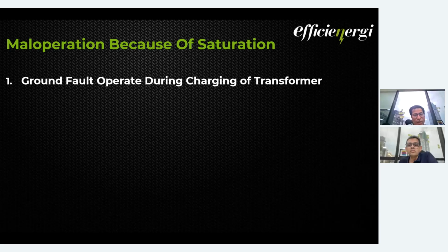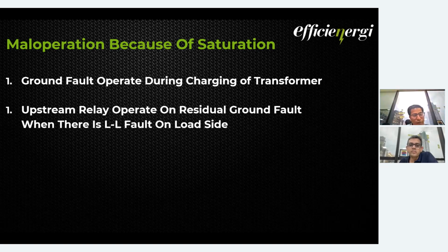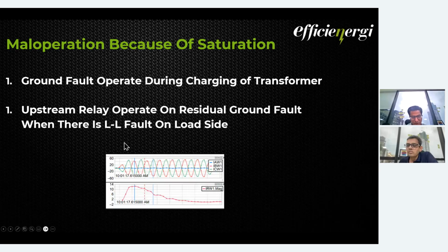Then there is a second case we see very often. That is when there is a line-to-line fault on a load side, but the upstream relay operates on residual ground fault. In the actual case, there is no ground fault happening on the load side. There is a simple line-to-line fault, but the upstream relay trips, and everything looks normal. But when we do the RCA, the first doubt that comes to our mind is CT saturation. So how does this happen? We have one waveform which will explain. I will just zoom in a bit.